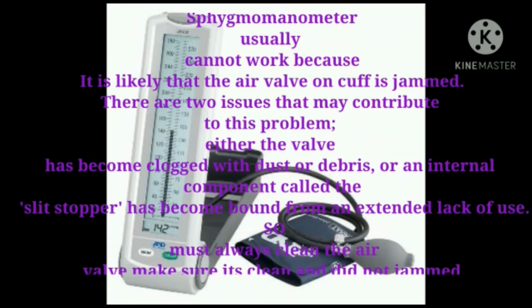A sphygmomanometer usually cannot work because it's likely that the air valve on the cuff is jammed. There are two issues that may contribute to this problem. Either the valve has become clogged with dust or debris, or an internal component called the slit stopper has become bound from an extended lack of use. So, to overcome this problem, you must always clean the air valve, and make sure it's clean and does not jam.